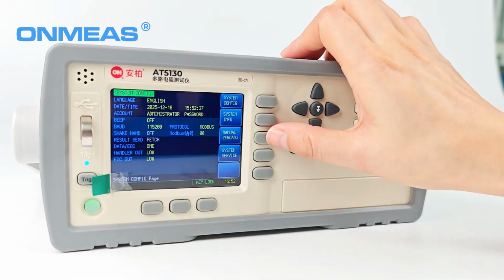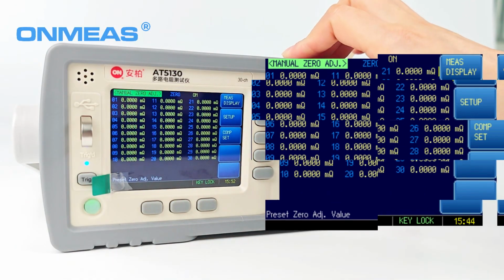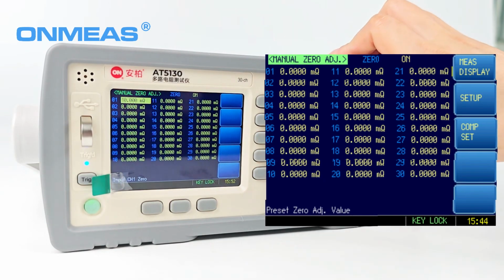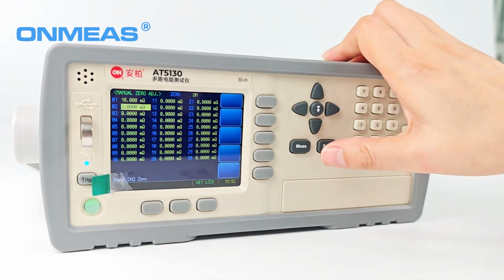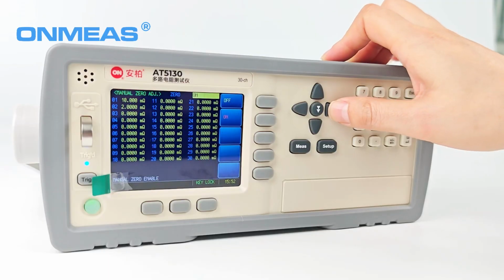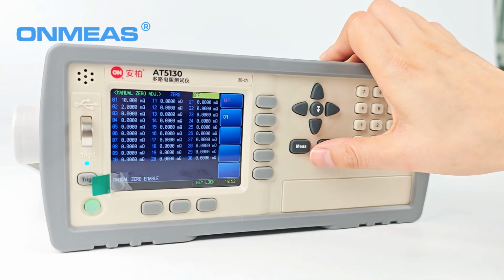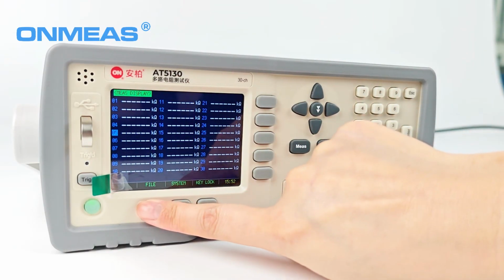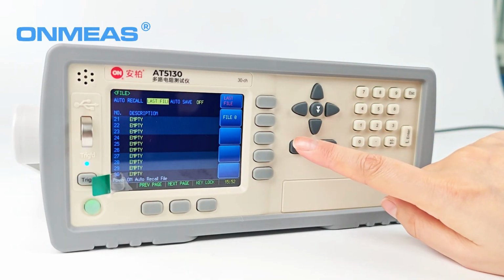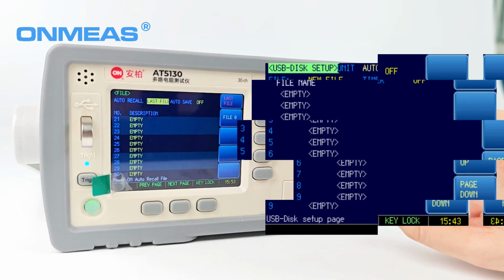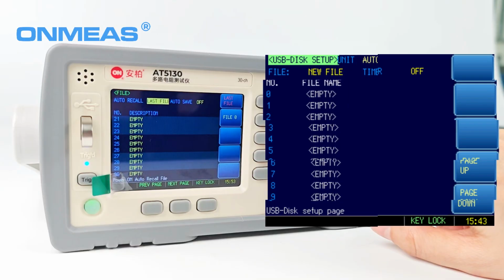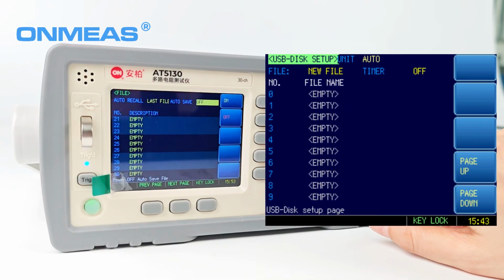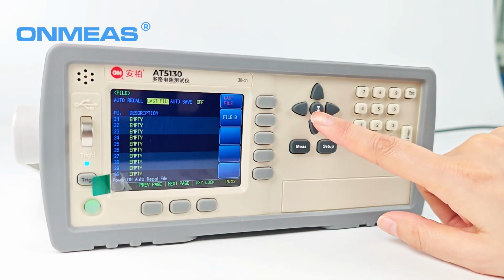On the system configuration page, press Zero Value Correction to enter the Zero Value Correction page. On this page, you can set whether to enable or disable Zero Value Correction, and you can also set the values for each channel. Press the bottom function key file to enter the file management page. The settings can be saved in up to 30 files, making it convenient to access them either when starting up or when changing the specifications.